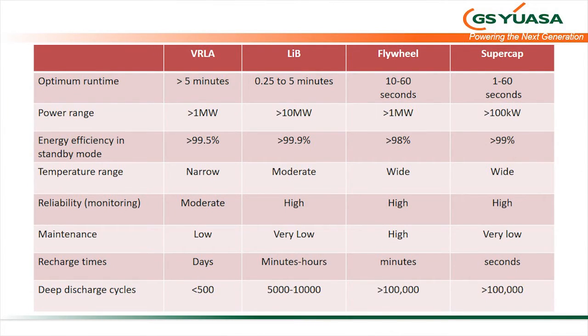But this is purely based on payment cost for the system. So bringing that together, almost to sum up, I've put this table together looking at the pros and cons for these different technologies and where the application points are. If you look at the optimum runtime, we would say the VRLA, once you get out beyond 5 minutes, 10 minutes, then it's the way to go. That's where you're starting to get good optimized performance out of that. Forget it if you're less than 5 minutes. They're just not designed to give those very high powers. The LIB, lithium ion, is probably good in the quarter of a minute to 5 minutes, and there's a crossover point somewhere.